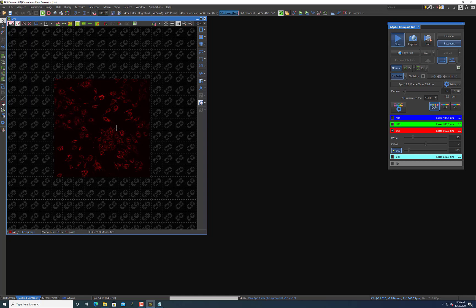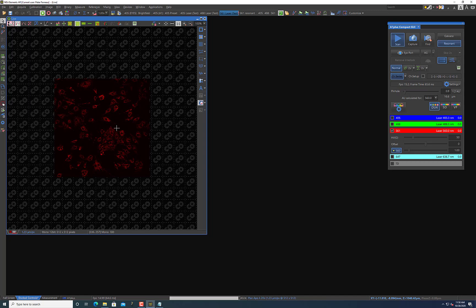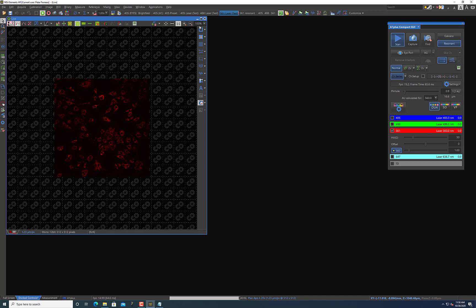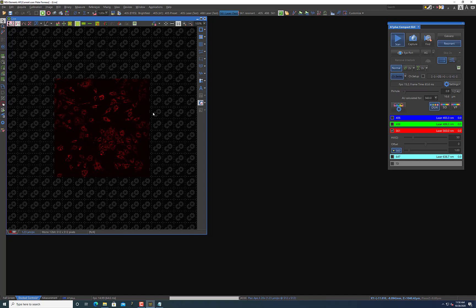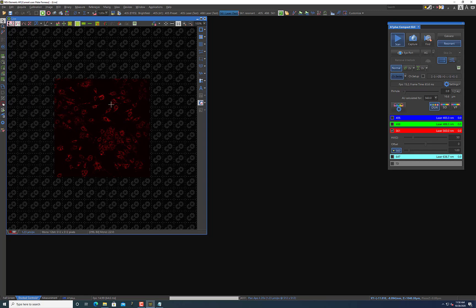Instead of using these sort of linear mechanisms to move the mirrors at different angles and produce the image like you see in the galvano mode, resonant uses the mirrors like a tuning fork, and so they oscillate between different angles. By doing that, it actually rapidly speeds up the imaging speed itself.